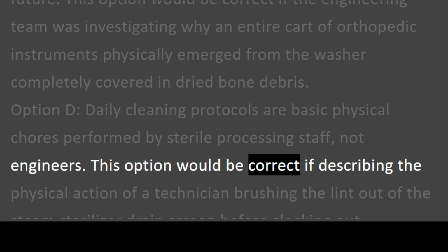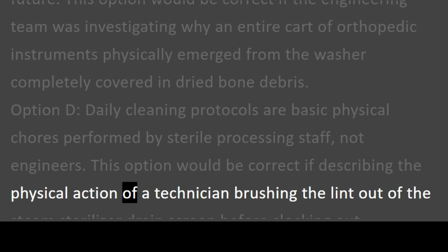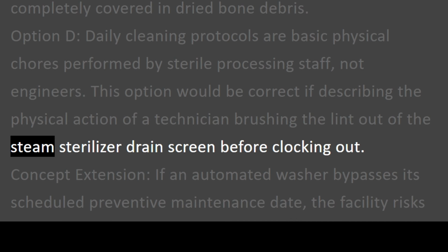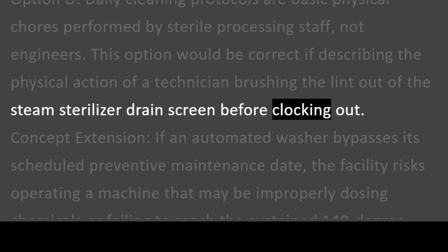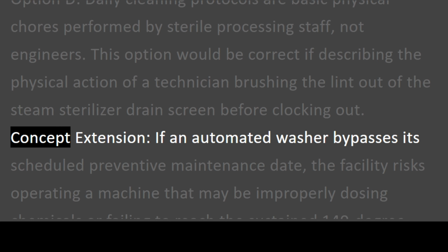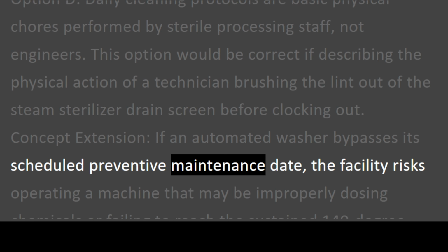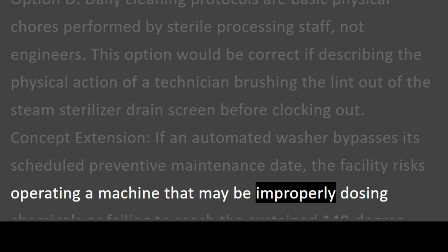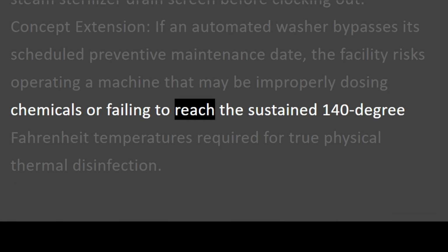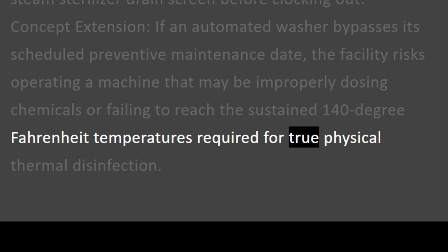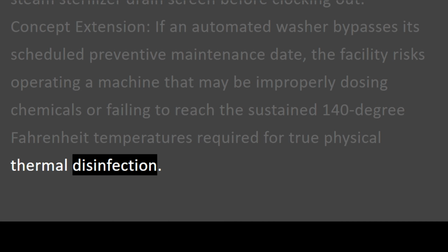This option would be correct if describing the physical action of a technician brushing the lint out of the steam sterilizer drain screen before clocking out. Concept extension. If an automated washer bypasses its scheduled preventive maintenance date, the facility risks operating a machine that may be improperly dosing chemicals or failing to reach the sustained 140 Fahrenheit temperatures required for true physical thermal disinfection.